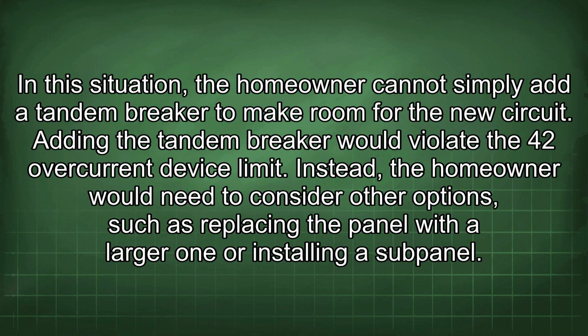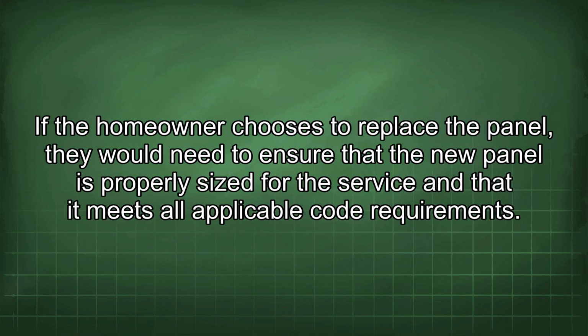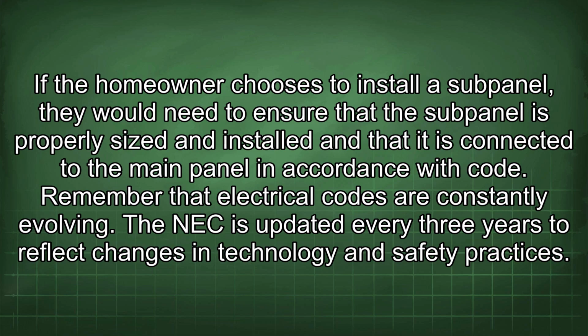Instead, the homeowner would need to consider other options, such as replacing the panel with a larger one or installing a subpanel. If the homeowner chooses to replace the panel, they would need to ensure that the new panel is properly sized for the service and that it meets all applicable code requirements. If the homeowner chooses to install a subpanel, they would need to ensure that the subpanel is properly sized and installed and that it is connected to the main panel in accordance with code.